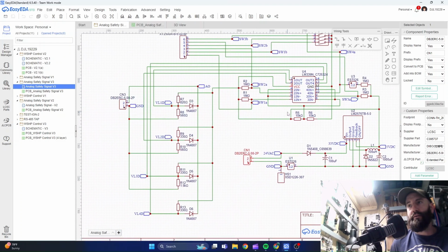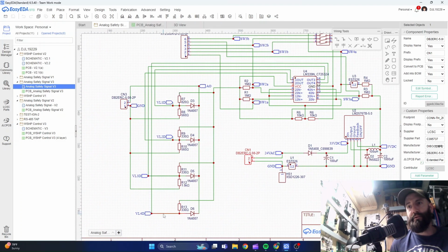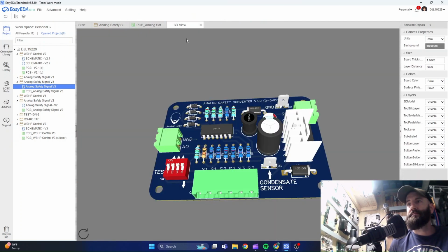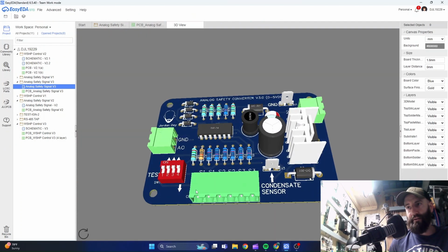When output 4 goes high, remember, it just kind of floats, or it behaves as if you just disconnected this. So our 5 volts is going to be able to feed through here, feed through our 330 ohm resistor, through our diode, and give us almost 5 volts. It's usually like 4.7 volts on our analog output going out. So now we still can read 4 distinct voltages coming out of our analog safety converter, but we're only using 3 dry contact safeties and 1 condensate sensor.